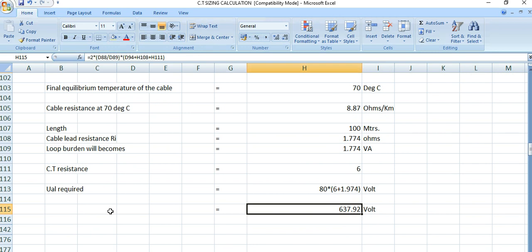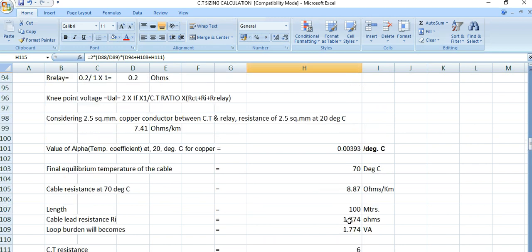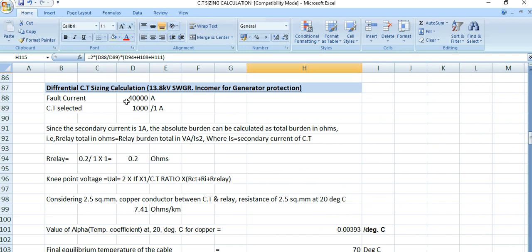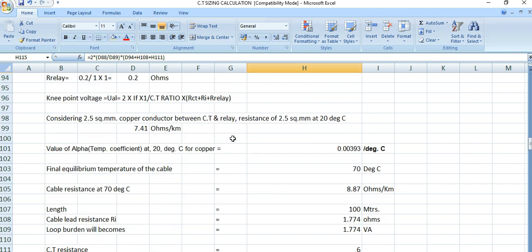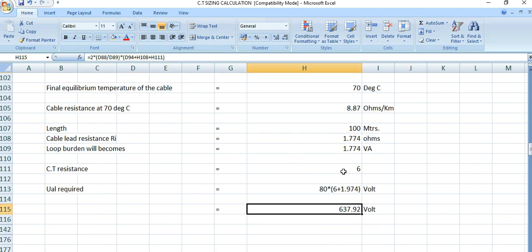637.92 volts — this is what we need to specify during CT procurement. The CT parameters to specify are: the knee point voltage V_k of 637.92 volts, and the CT ratio of 1000/1 ampere. For this differential protection CT, the knee point voltage must be mentioned for the procurement activity. This is the differential CT selection — if the CT resistance is more, the knee point voltage will also change accordingly.